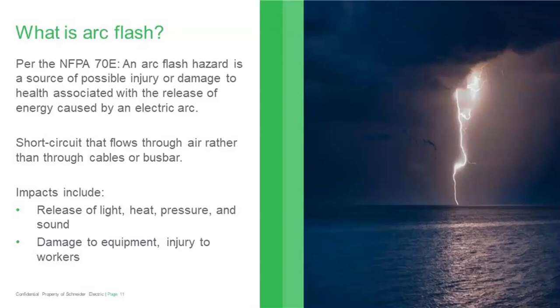The arc itself has an impedance, with a high level of current flowing through it, maybe tens of thousands of amps in some cases. We're delivering a whole lot of power essentially to a load. Even on a low voltage system, you can be delivering several megawatts worth of power to that arc flash event, and there's enough energy released as a result to cause a pretty significant release of light, heat, pressure, and sound.